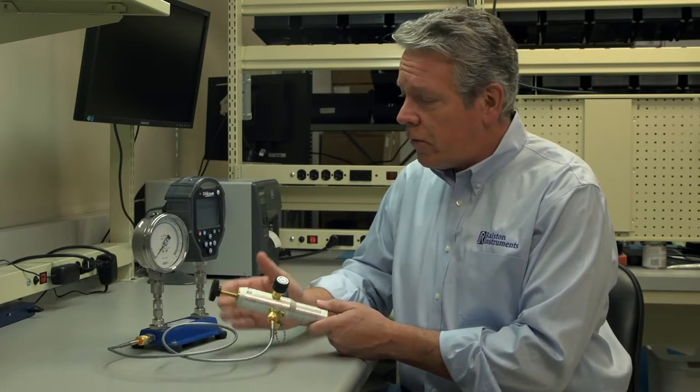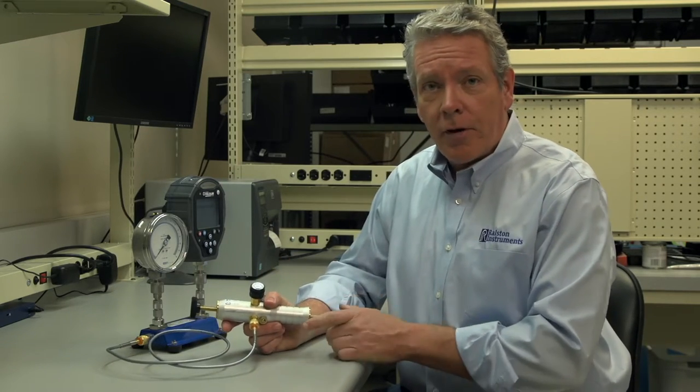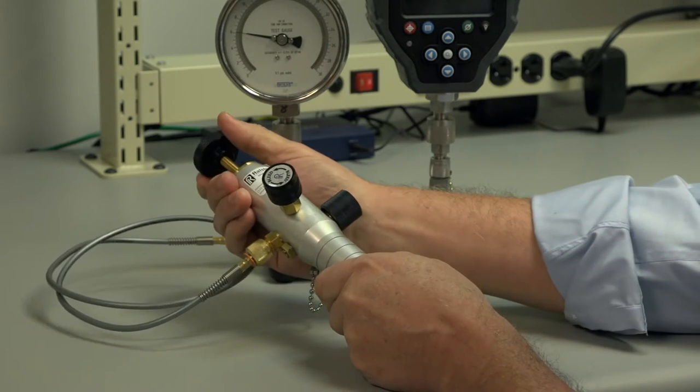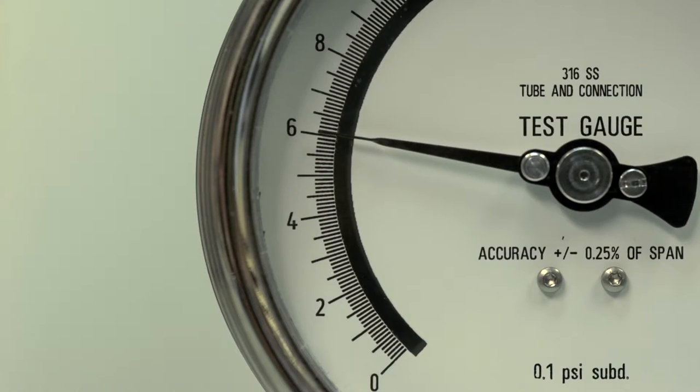Now we'll apply pressure to achieve a reading of our cardinal point on the device under test, and then we'll precisely dial in with a vernier so our needle falls exactly on six psi. Since it does fall on a major hash mark it makes the setting much easier and more accurate.